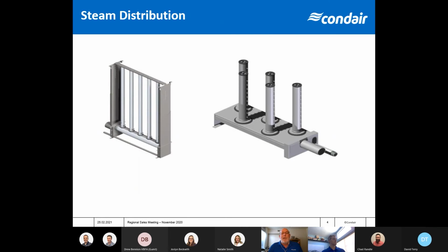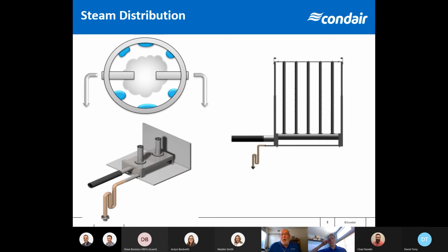Next, I want to talk about steam distribution just a little bit. So these are our 2 grid type system short absorption manifolds. So on the right here, we show our mini short absorption manifold. These are great for real small duct work. And on the left there is our standard short absorption manifold. This is what we use on the medium to large ducts and air handling units. So these are all designed to absorb that steam into the air very, very quickly.